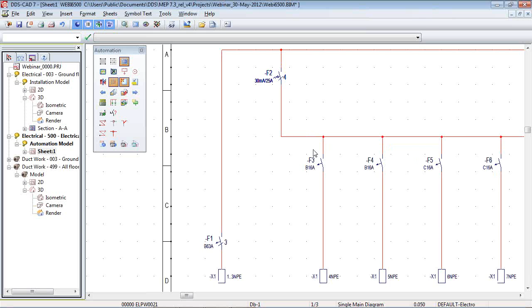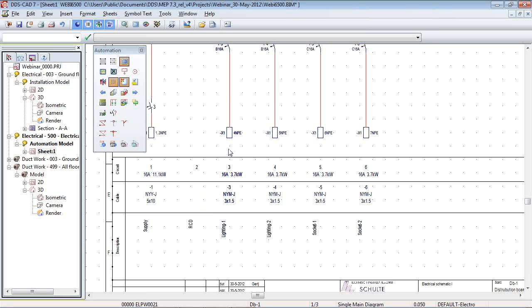But I can also say, okay, I don't want to have a diversity factor of 1. I would like to have a diversity factor of 0.5, for both, and this will indicate that my nominal power of my RCD is still in range.